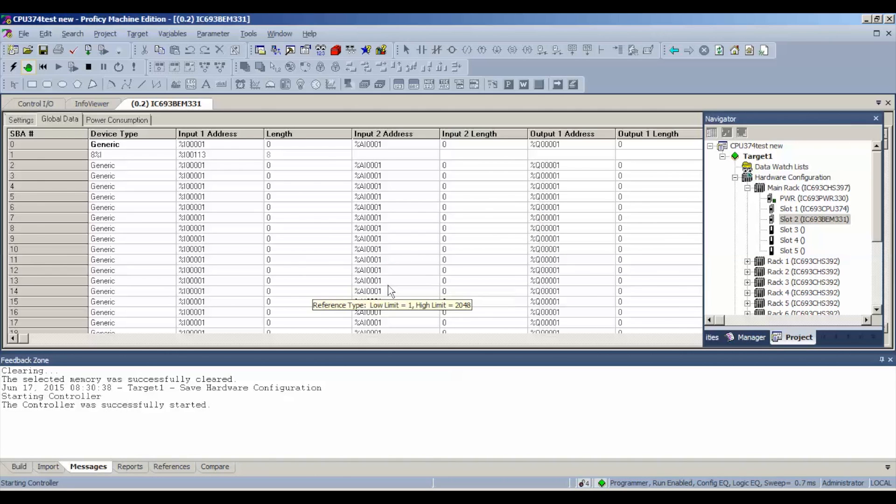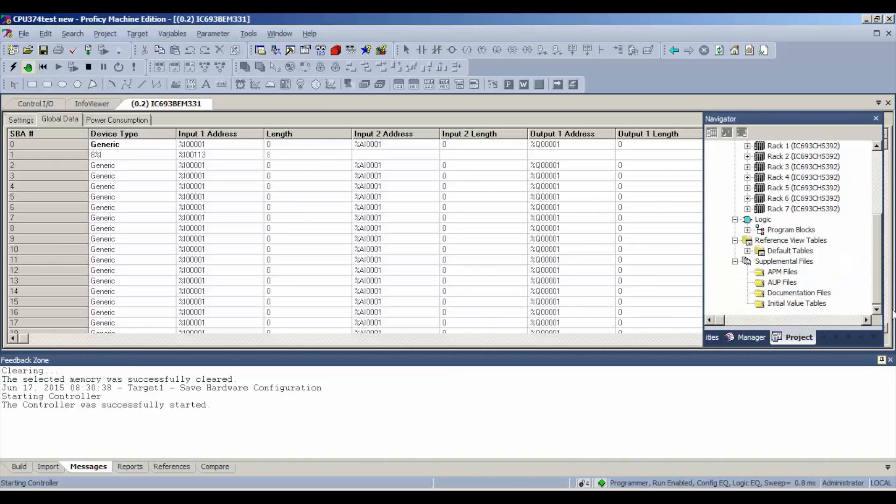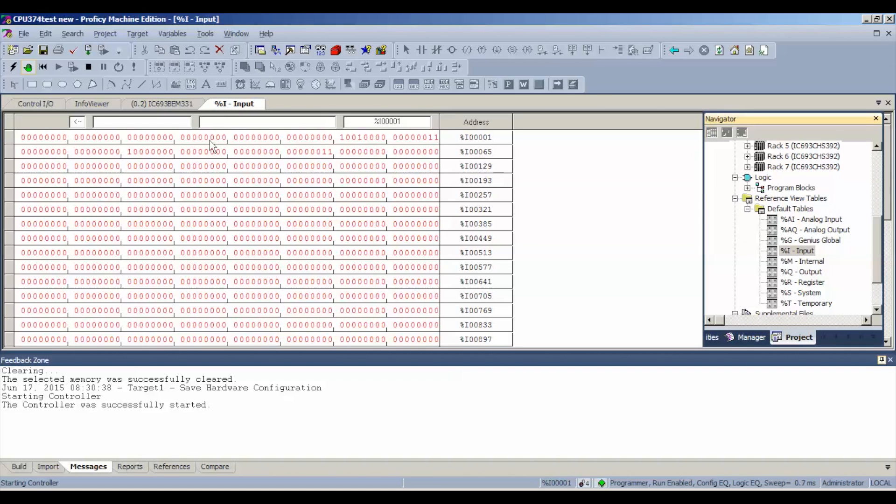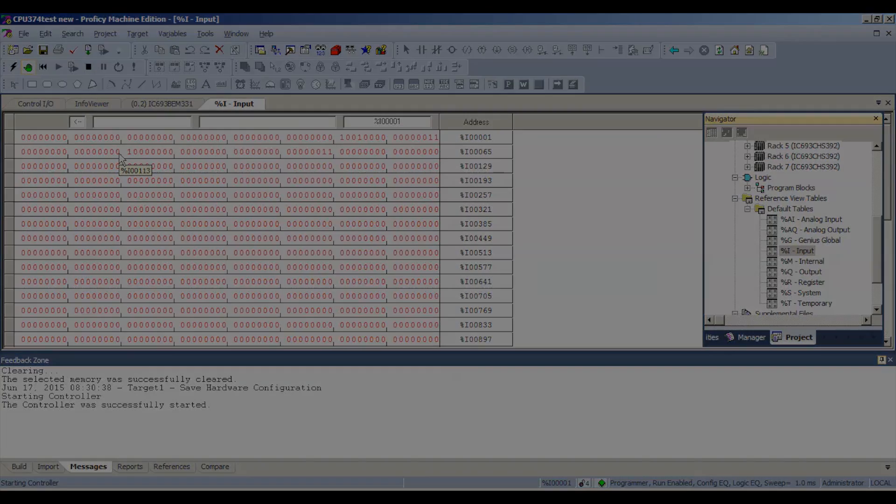Okay. Now, at this point, you should be programmer mode, run enabled, configuration equal, logic equal, and your processor should have all three lights on, or rather the processor should be reporting to the power supply to be in run mode. Now the next thing I'm going to do, since I'm in Proficy Machine Edition, is go down to my default tables and expand that, go to my inputs, and I'm going to bring my arrow over here to where our inputs are going to be coming in. At the tip of my arrow, you can see as I'm hovering over it, it says %I00113. That's where I'm going to start to look for my input activity. We're going to toggle these zeros to ones by probing.